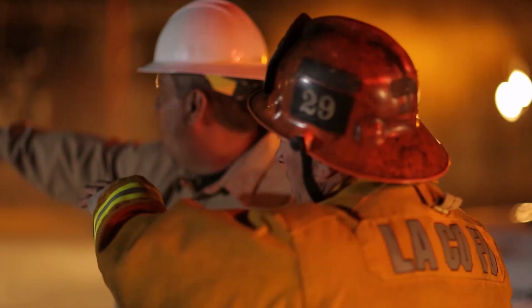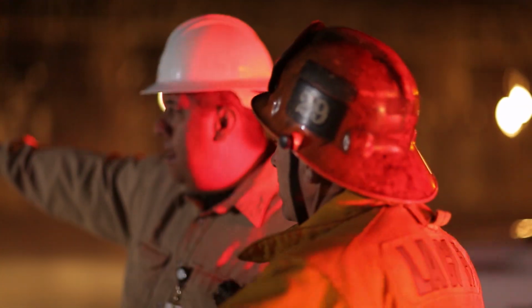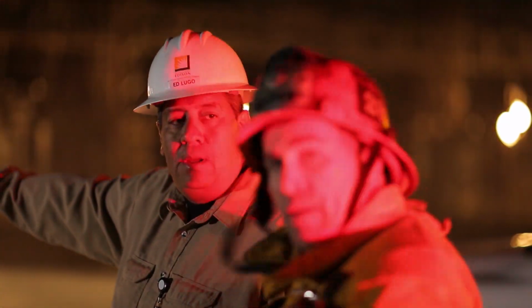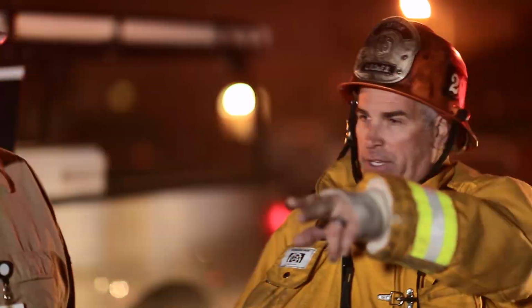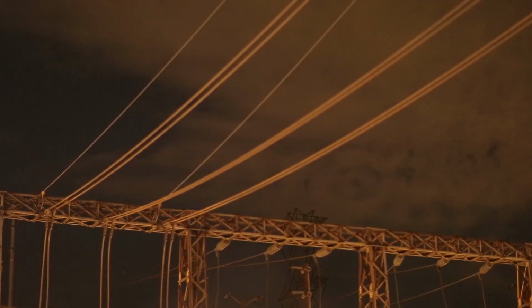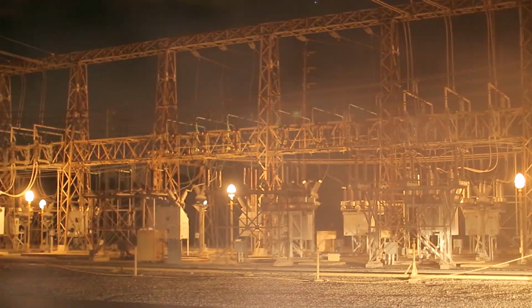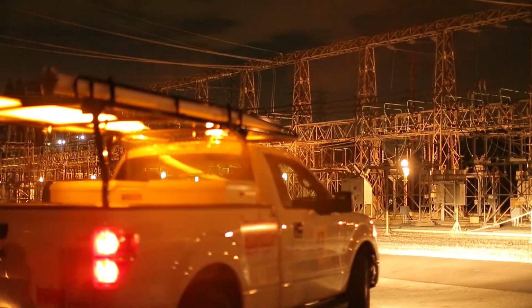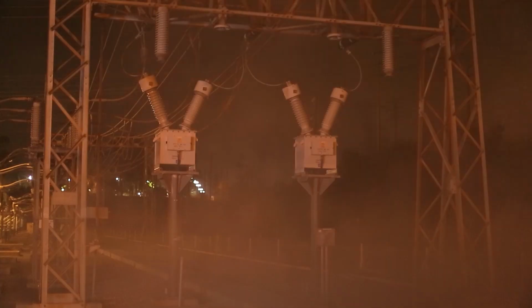Rescue operations should only be conducted on or near equipment that has been de-energized and made safe by us. The incident commander should stay in close communication with our on-scene representative throughout the duration of the incident. The hazards you could encounter in a substation include high voltage lines, both overhead and underground, open high voltage buswork crisscrossing the station at relatively low height. Never drive beneath overhead structures without specific approval.